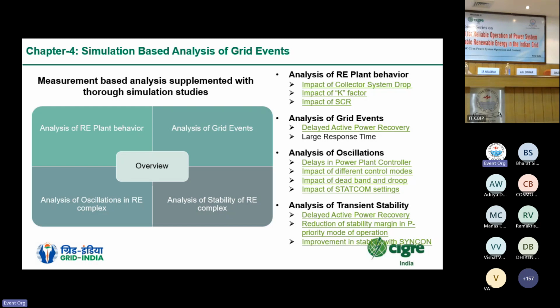Again, the short circuit ratio which RE plants had taken as a reference to tune their voltage controllers was different from the short circuit ratio present at the site in the operating phase. In the operation phase, the short circuit ratio varies based on different load generation scenarios, and since the RE plants' controllers were tuned only to a particular short circuit ratio, they were not able to display that behavior accurately. So in the analysis of grid events, the simulation-based studies helped us identify that one of the reasons for the difference from the desired performance was the delayed active power recovery of the RE plants. The second point identified was that some plants had a large response time compared to what was desired of them.